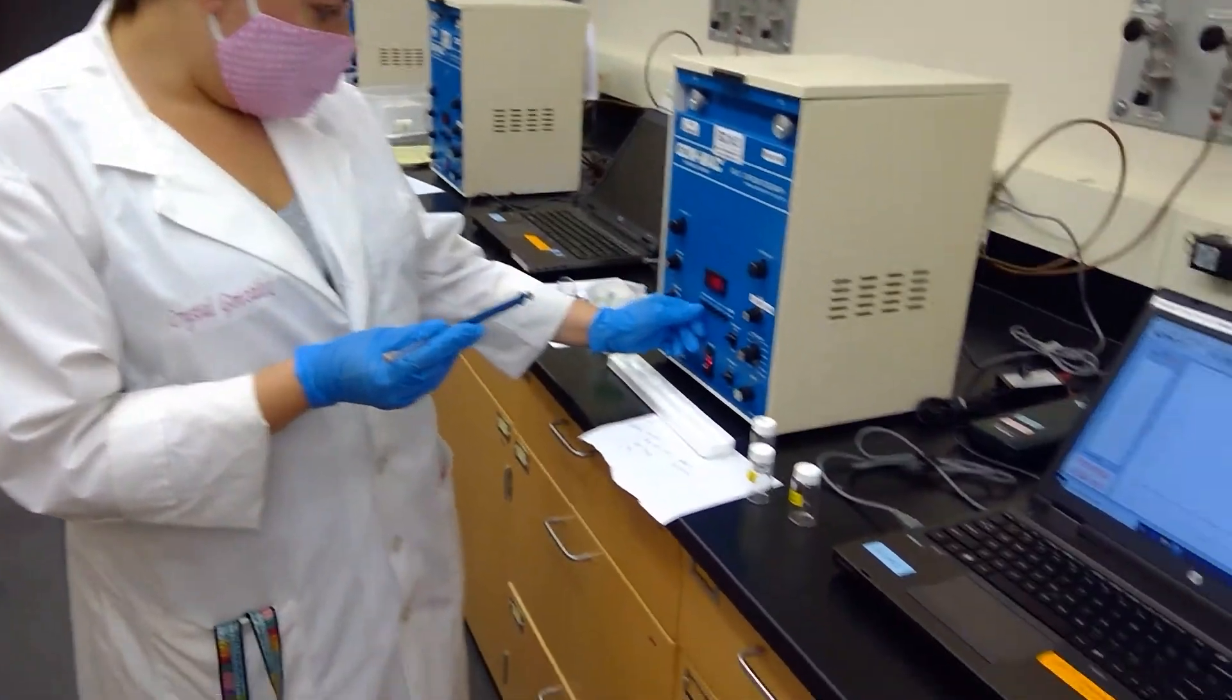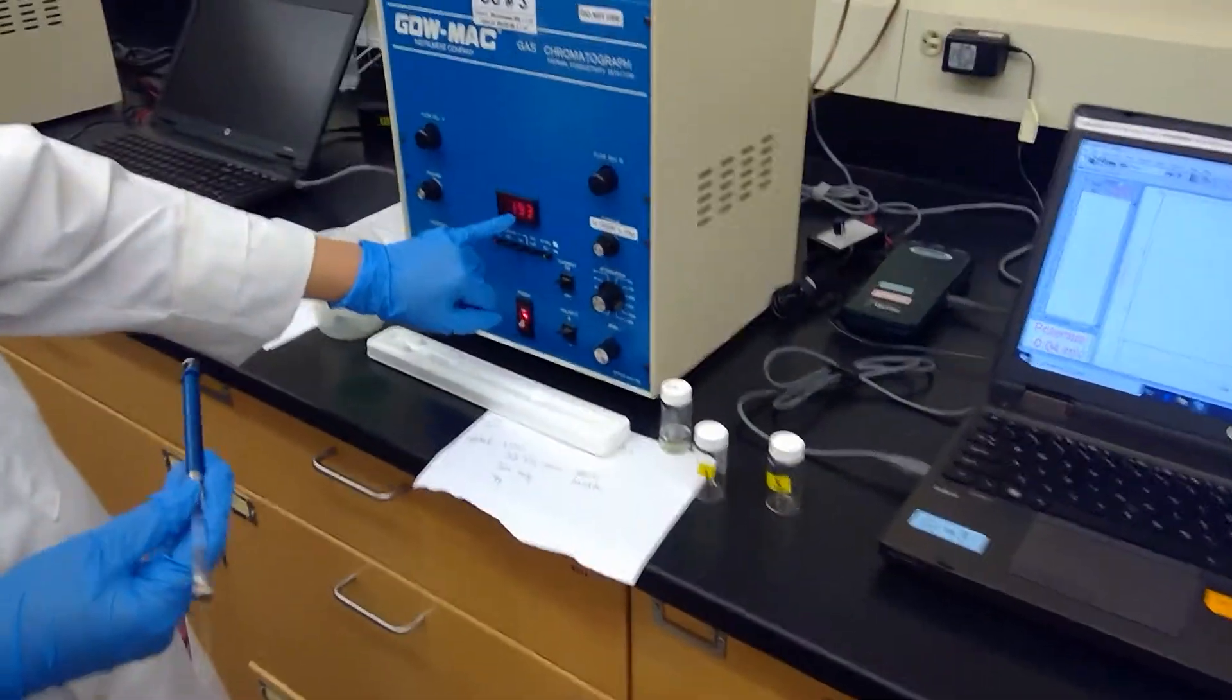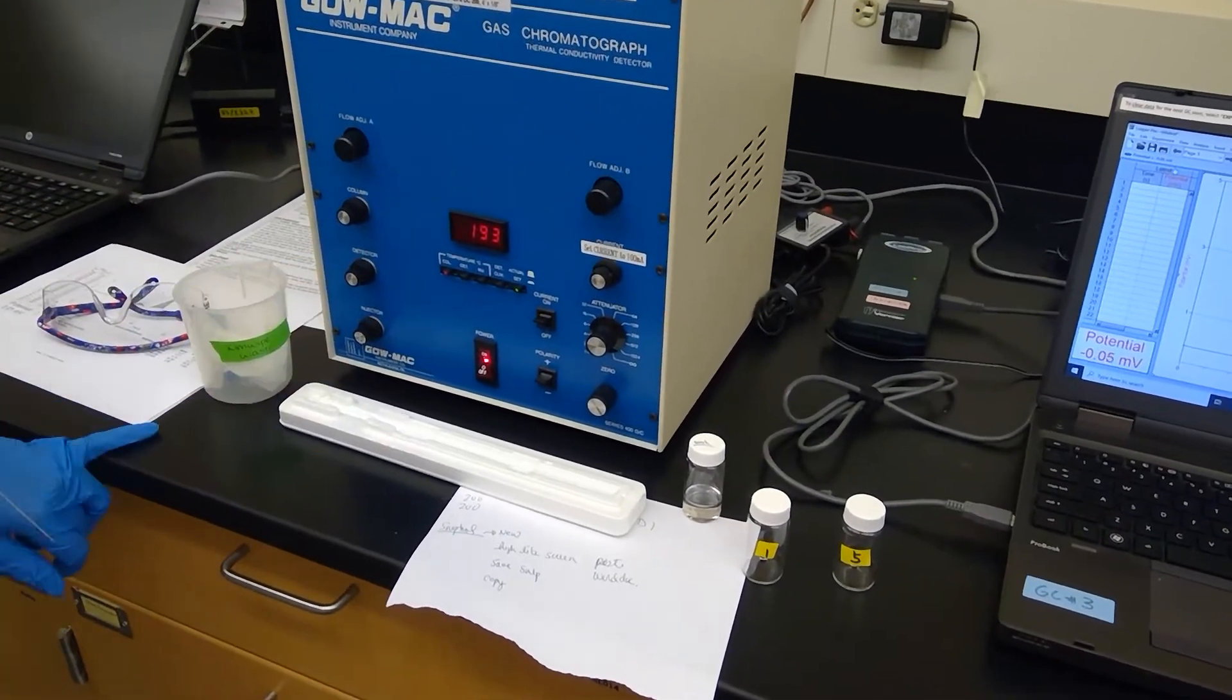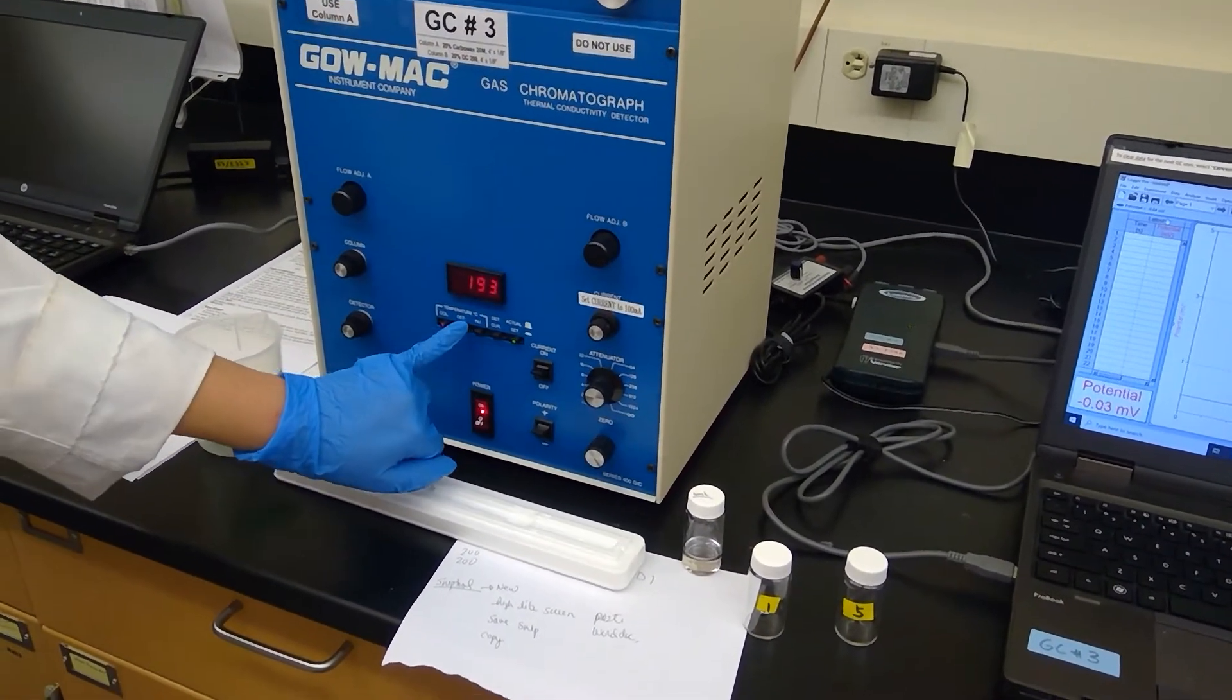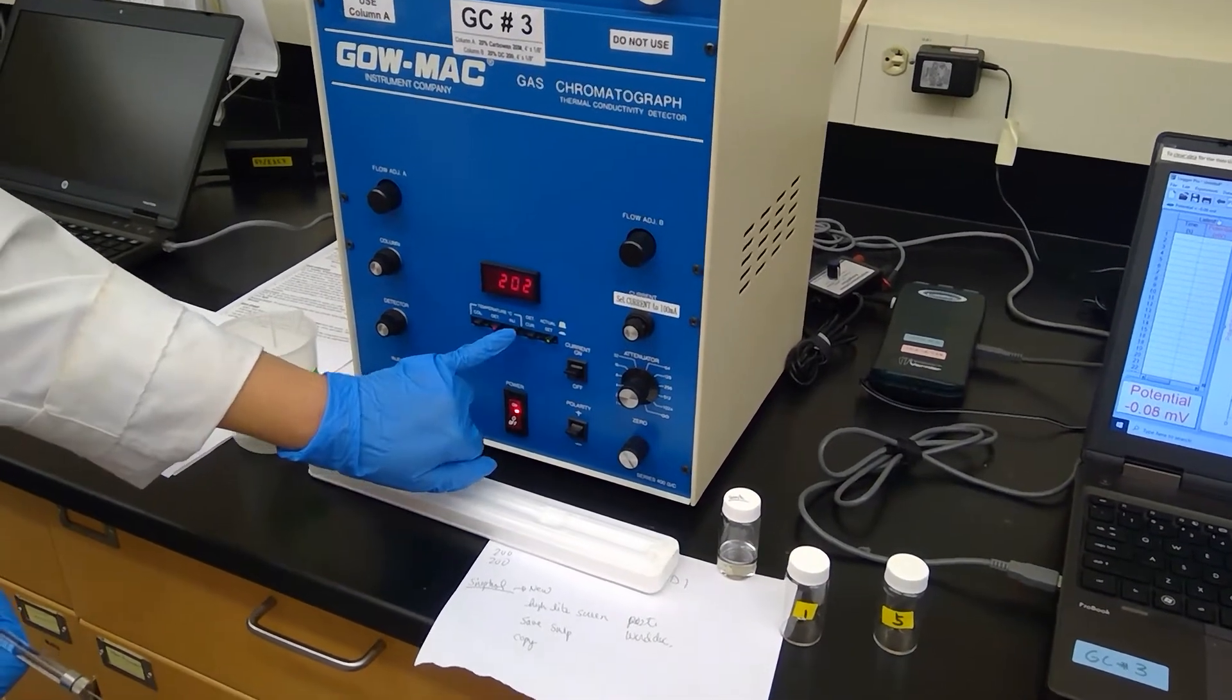So if we take a look here, I'm going to go ahead and press a couple buttons and show you that our column temperature is actually quite hot. So this is in degrees Celsius. Our column is currently at 193 degrees Celsius.